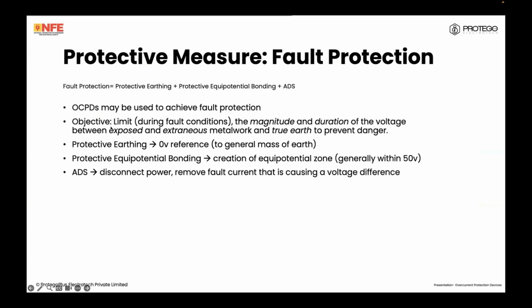The objective is we want to limit during fault conditions the magnitude and duration of voltages that may appear between exposed and extraneous metalwork and the true earth, which is essentially establishing what is called an equipotential zone. The protective earthing provides this zone a 0 volt reference, and therefore to the general mass of earth, and the equipotential bonding creates the zone. Generally, for normal installation, this is 50 volts, and the automatic disconnection of supply through the OCPD will disconnect the power and remove the fault current that is causing a voltage difference. Plain and simple. This is what we are focusing on here.